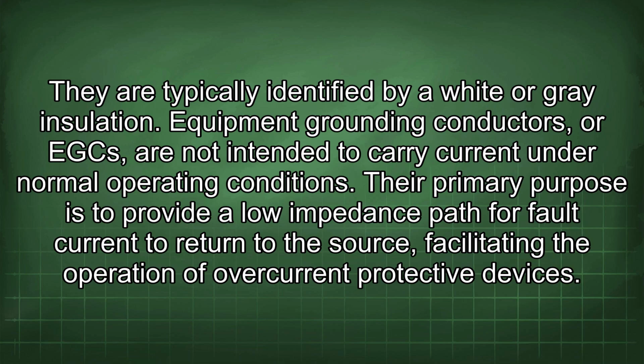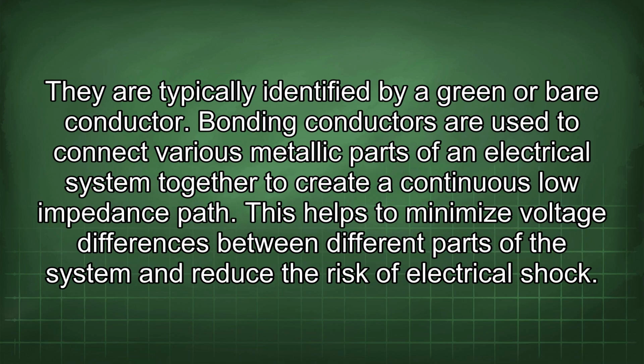Equipment grounding conductors, or EGCs, are not intended to carry current under normal operating conditions. Their primary purpose is to provide a low impedance path for fault current to return to the source, facilitating the operation of overcurrent protective devices. They are typically identified by a green or bare conductor. Bonding conductors are used to connect various metallic parts of an electrical system together to create a continuous low impedance path. This helps to minimize voltage differences between different parts of the system and reduce the risk of electrical shock.